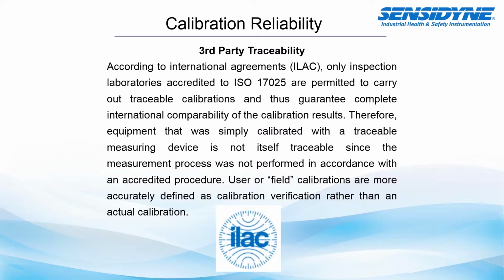User or field calibrations are more accurately defined as a calibration verification rather than an actual calibration itself. So it's important to note that when we do these field verifications, it has a little bit different of a connotation to it than an actual calibration of an instrument where you are making adjustments to the calibrated process.